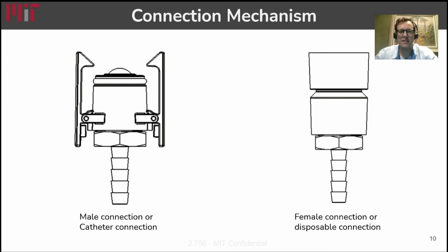Our connection design is composed of two terminals. On the left, we have the male connection or the catheter connection, which is attached to the patient. On the right, we have the female or disposable connection that is connected to the dialysate fluid. They work by axially mating two spheres that push each other, allowing fluid to flow.